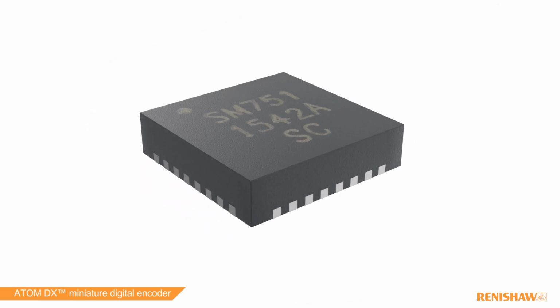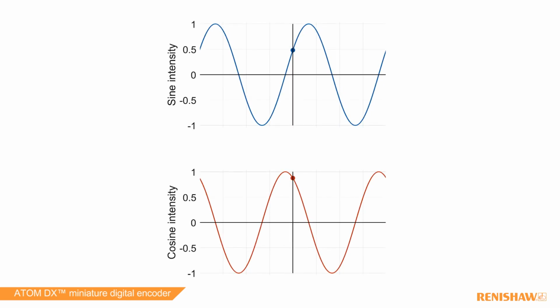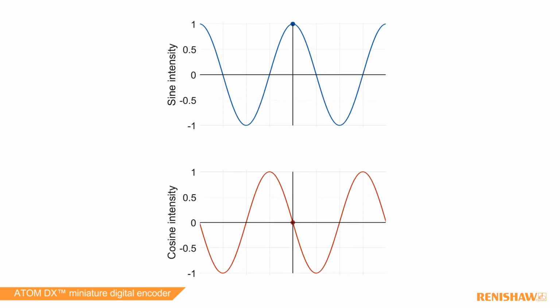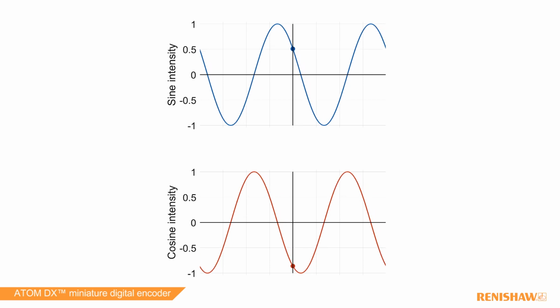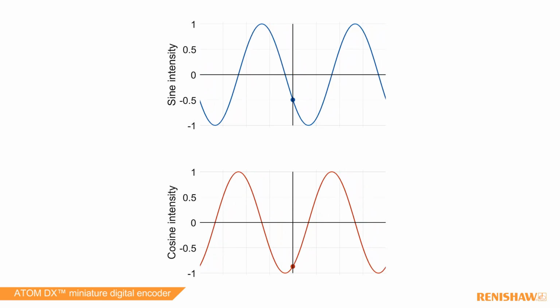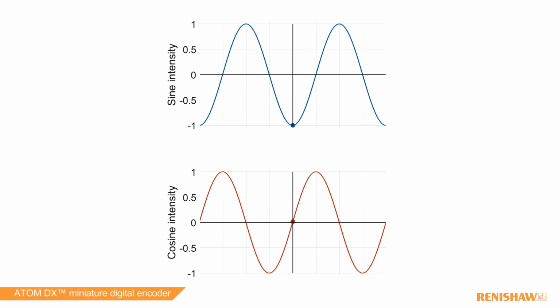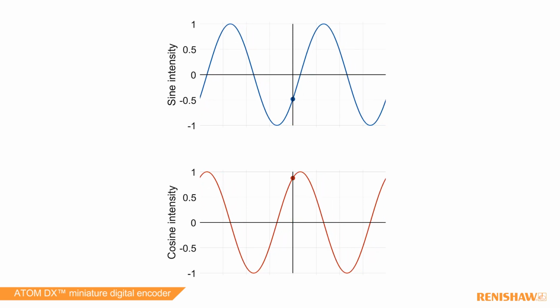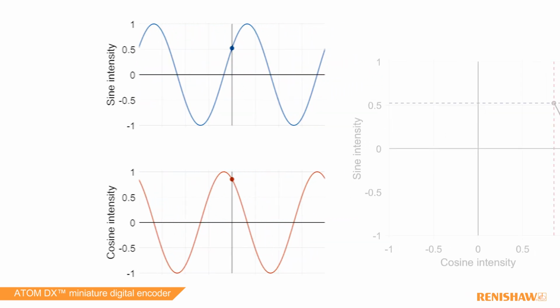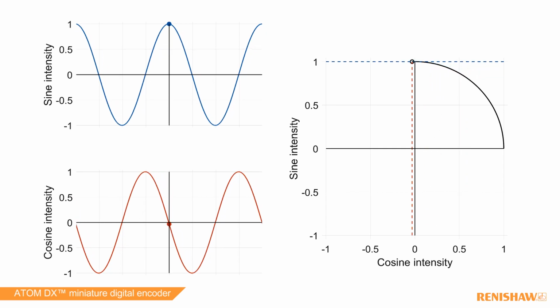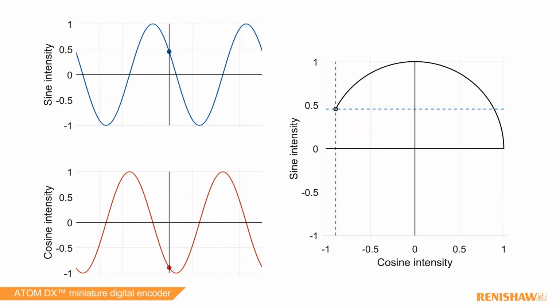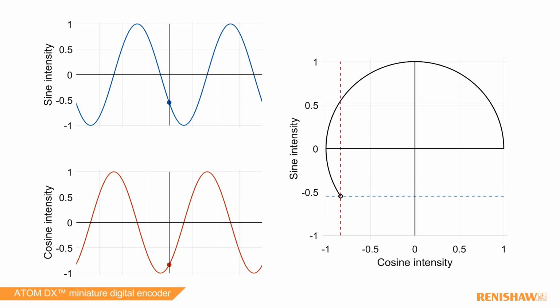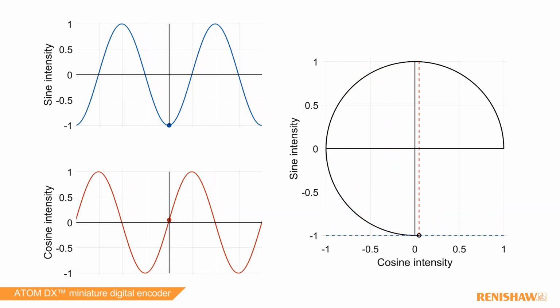Analog output signals from position encoders generally take the form of sine waves in quadrature - in other words, a sine and a cosine signal 90 degrees apart in phase. These signals indicate change of position and direction of motion. If these quadrature signals are plotted against each other, they form a circular Lissajous figure. As the encoder moves, the signals move around the circular plot, once for every scale period.